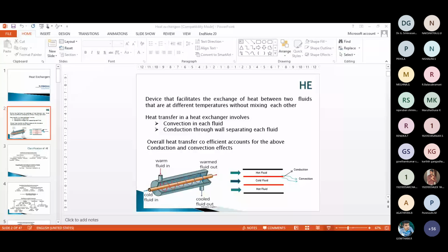Based on the flow of fluid within the heat exchanger, it is classified again into two groups. One is single pass, another one is multi-pass. Single pass means the fluid enters either the shell side or tube side, and it leaves on the other side. That is called a single pass. If you return the fluid within the tube or shell side, then it is called multi-pass. Based on single pass and multi-pass, this is classified into different flows: counter flow, parallel flow, cross flow, split flow, and divided flow.